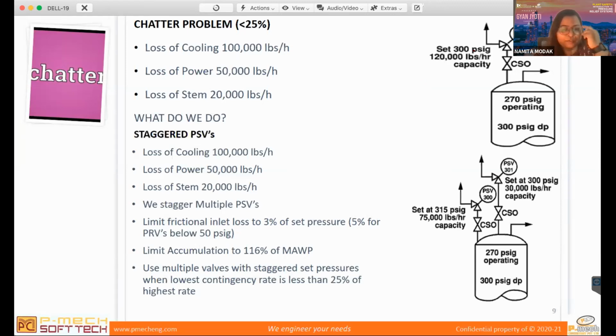I mean, there is a lot of design margin, whatever is required. So in this case, that chattering will happen. So what is the solution to it? You can give two small PSVs. See here, I have given two PSVs. One is set at 30,000 lbs per hour and another at 75,000. So in this way, when loss of steam happens, this PSV can cater.